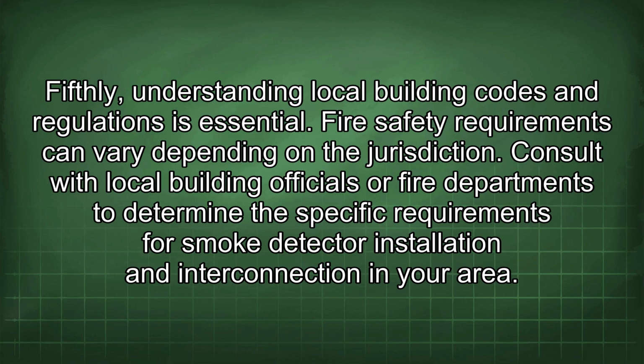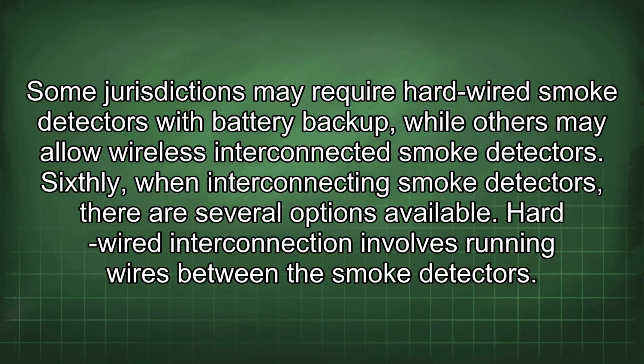Fifthly, understanding local building codes and regulations is essential. Fire safety requirements can vary depending on the jurisdiction. Consult with local building officials or fire departments to determine the specific requirements for smoke detector installation and interconnection in your area. Some jurisdictions may require hardwired smoke detectors with battery backup, while others may allow wireless interconnected smoke detectors.